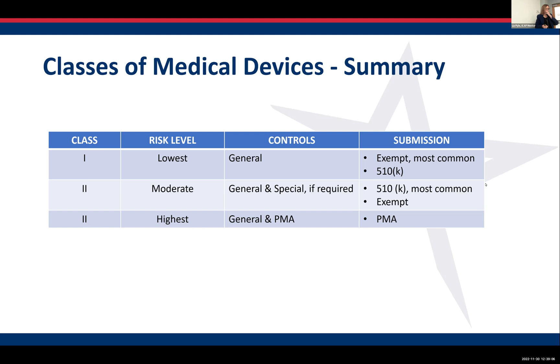So I mentioned the word general controls. Well, each classification has its own long list of general controls. So, and it starts with class 1. So class 2, they have to meet class 1 general controls and class 2 general controls. Class 3 has to do class 1, 2, and 3. So they build on each other, but this is just an example. These are by far not the whole list, but these are just an example of what some of the controls are that you may not have thought about. Labeling. Labeling is a big thing of control. Does it provide good information? It's medical device reporting. You have to report if there's any injuries, if there is any deaths, if there's any recalls. You're required to report that.